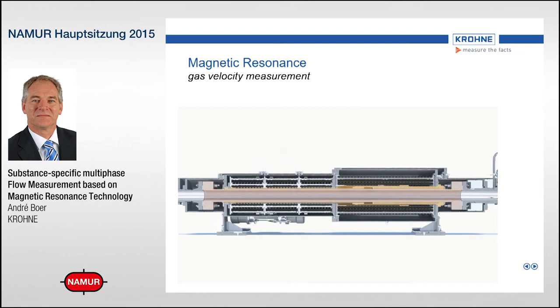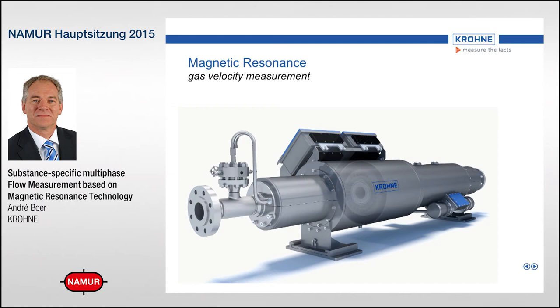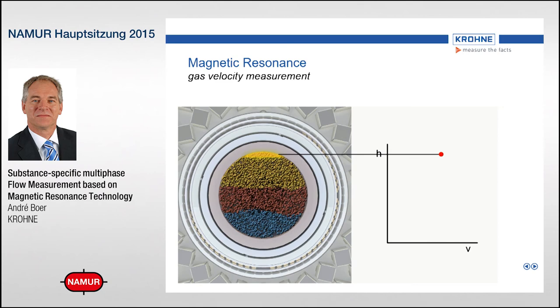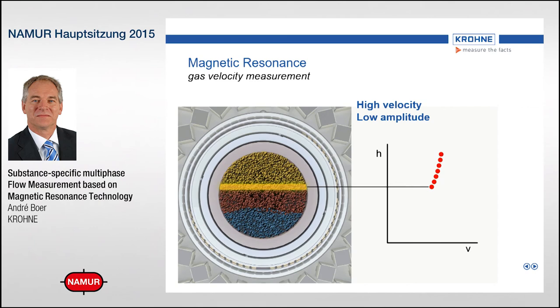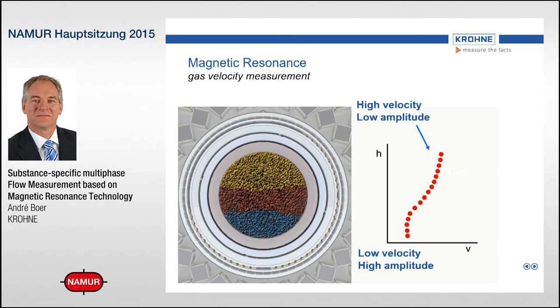The difficult part is the gas velocity measurement, because gas gives very small signals. Fortunately, as you may know from MRI in hospitals, you can also do imaging — and that's what we do here. In the cross-section, we can look for velocities per small slice. We divide the cross-section of the pipe into 16 individual slices and repeat the measurements we did before, so we can measure the velocity per slice and the amplitude per slice — giving us an enormous amount of information about what is happening inside that pipe.